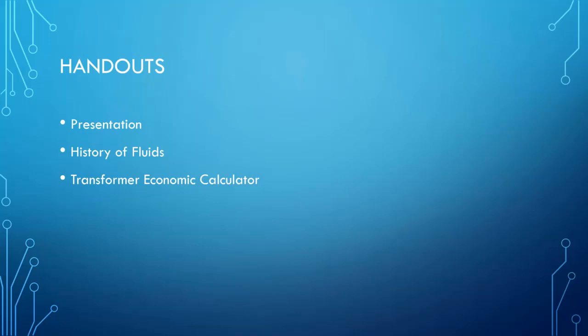I'll add a comment on the FM. One thing is that all manufacturers can build to the FM standard. Everyone has a copy of that standard, so they can add the additional accessories, the additional pressure relief devices. To label a unit with the FM label, certain additional accessories have to be added. So all manufacturers can build to the FM label requirements. It's just physically putting that label on the transformer that is not necessarily required, because you can still get the transformer designed with everything and just not have the sticker on it. So that's one thing to consider. If you want to open up the field to more than two bidders, you can state that it must be designed to the FM Global standards, but does not require the actual FM label.